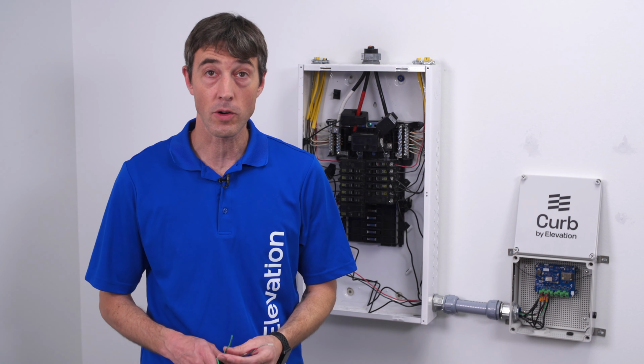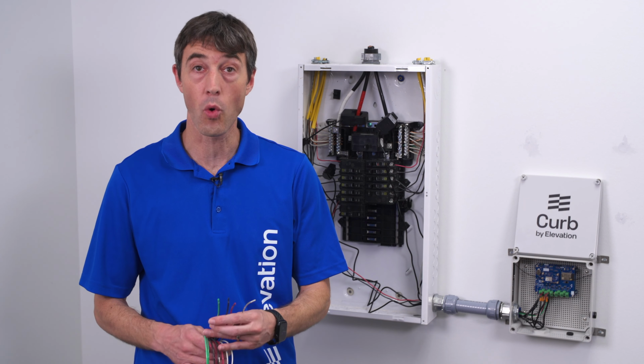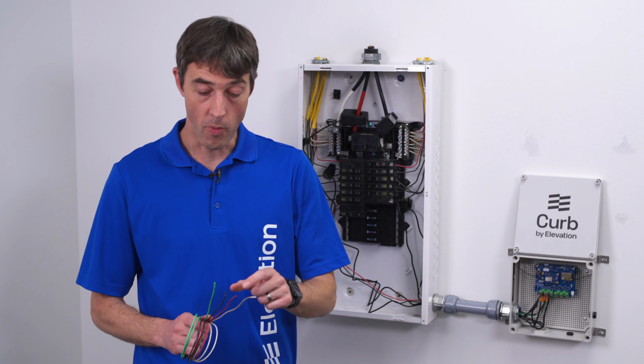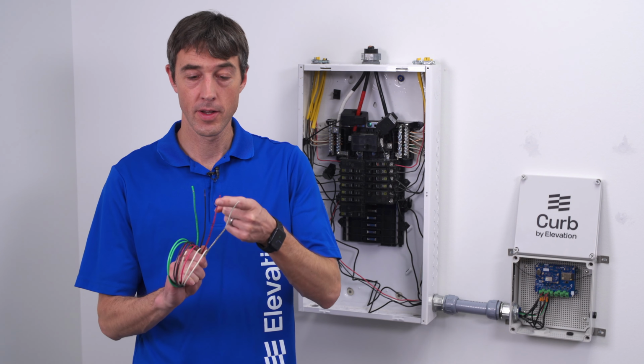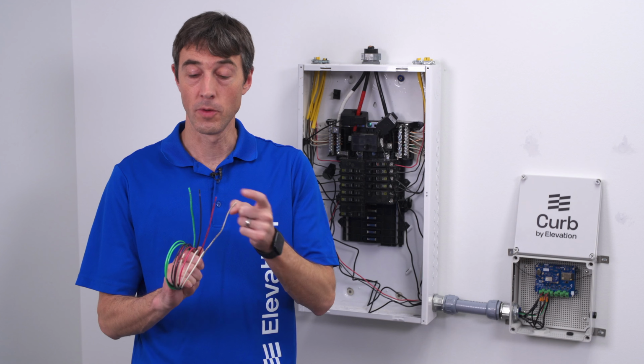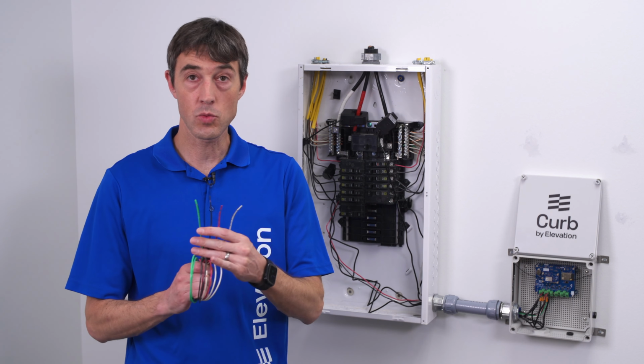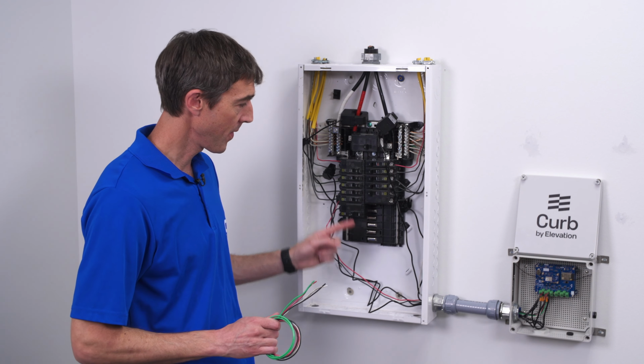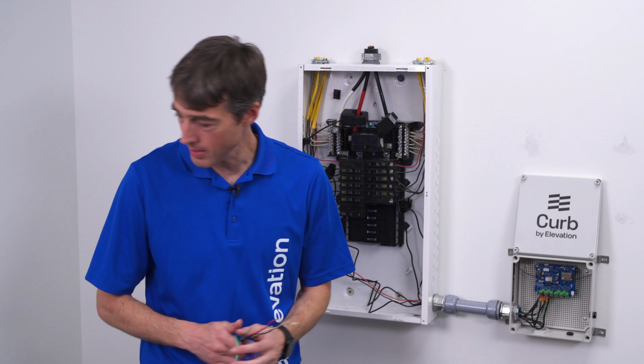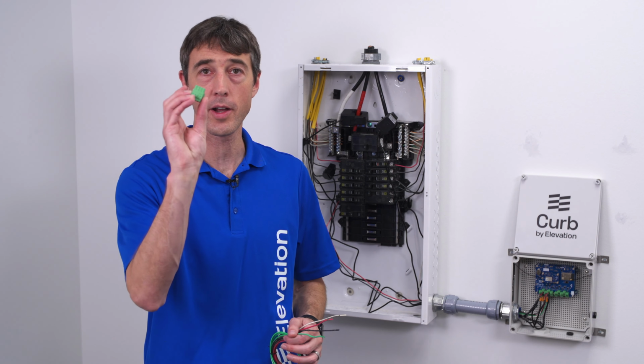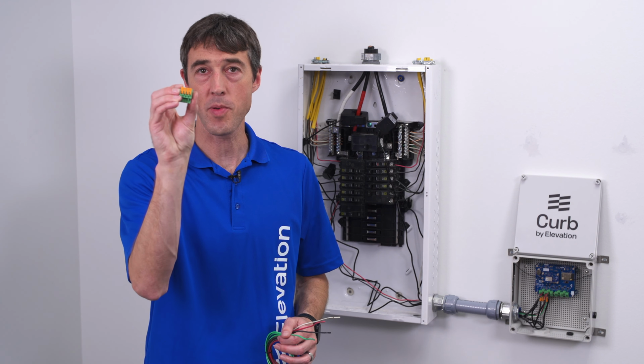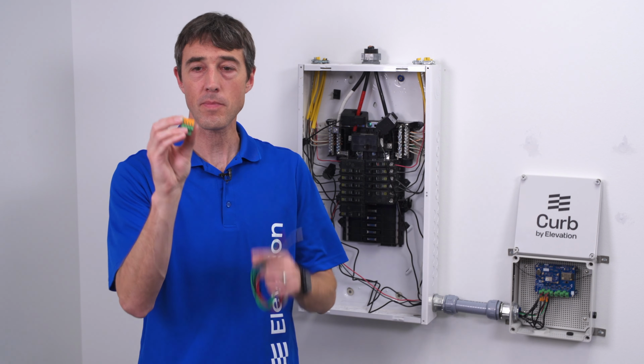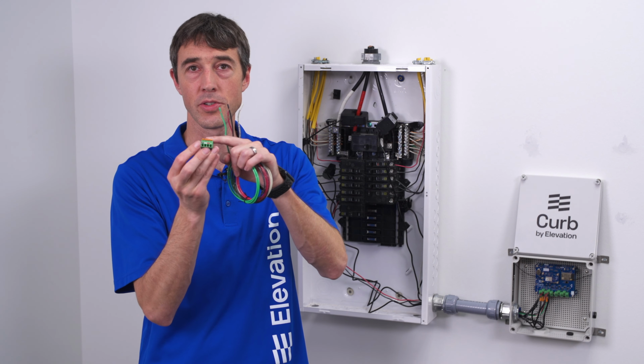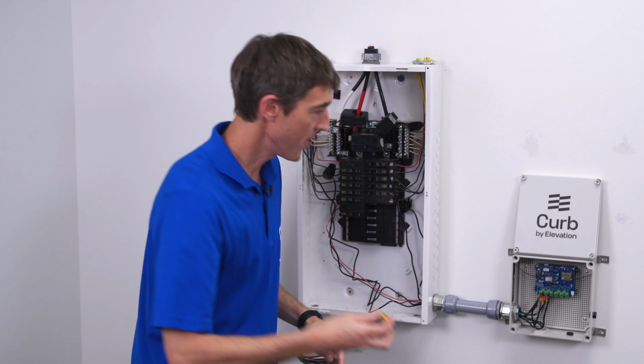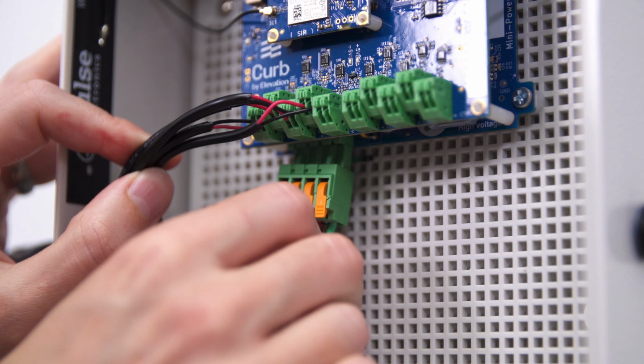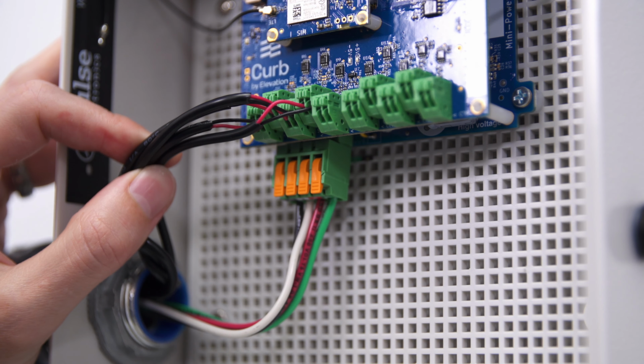The Curb needs to be connected through 4 individual wires. There's a wire for line 1, line 2, a neutral, and a ground. All of these wires come from the electrical panel, then get routed through the conduit and get connected into the power block connector, where they simply snap in to these orange ports and to the corresponding labels in this connector. This connector then gets installed into the bottom of the Curb device and powers the Curb device.